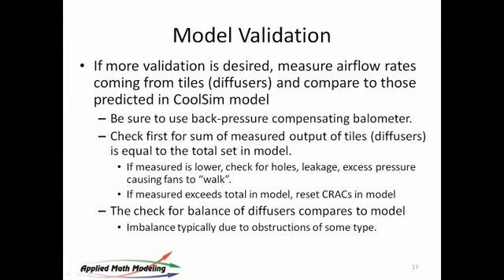So if more model validation is required, you can go to a next level. The next level is to measure the airflow rates coming from the tiles or the diffusers, depending on the kind of data center, and compare those with that predicted in the model. Now, this gets a little more difficult, a little more involved in terms of time, because you have to make measurements. And measurements are, by definition, subject to error, human error. First of all, we'd recommend you use a back pressure compensated balometer. Those can vary. If they're not back pressure compensated, we've learned that these can be off by up to 30%.